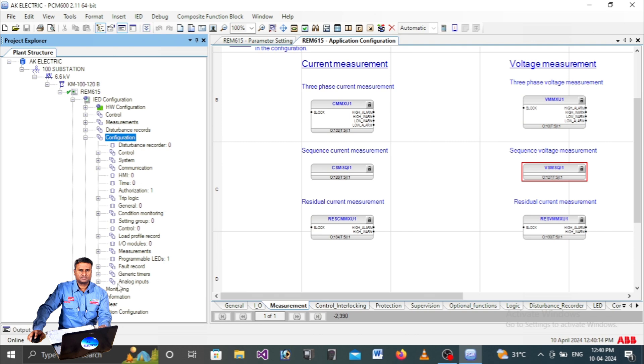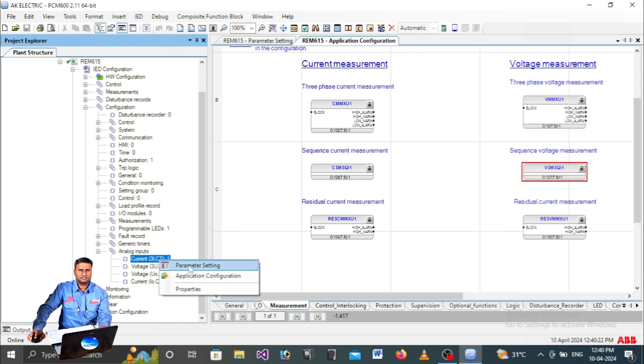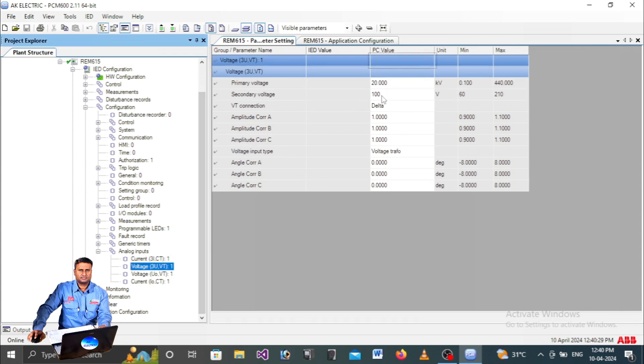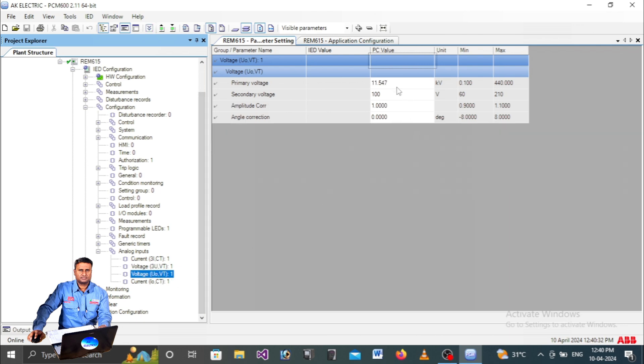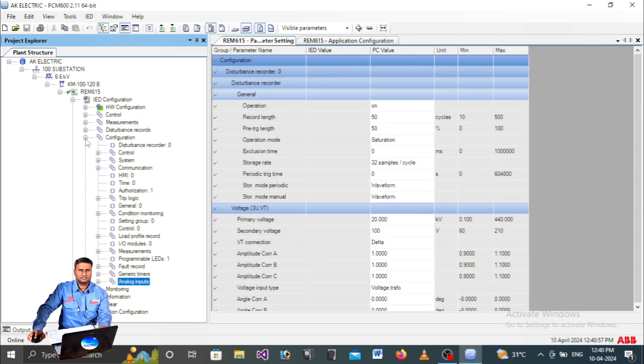Under Analog Inputs, right-click the three-phase CT and select Parameter Setting. Here you can see the primary current is 100 and secondary current is 1. For voltage, it shows 20 and 100. There is also a core balance CT at 100/1. These are all default settings from the factory - they come with the switchgear when delivered. These are not the current actual settings in the relay.